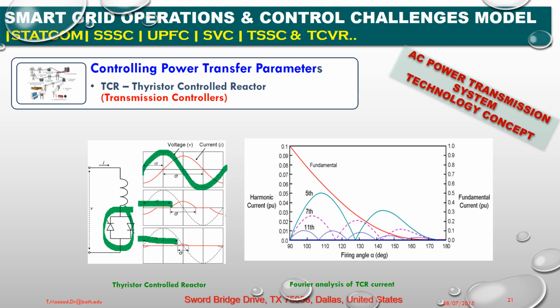Now on my right hand side, harmonic content versus firing angle, and red is my fundamental current. If we maintain 90 degrees, the 11th, 7th and 5th harmonic content will be present. As the firing angle increases from 90 to 120 degrees, the 11th and 7th reduce, and at 180 degrees they are eliminated or diminished. So 3-level quasi harmonic neutralized 48 pulse modulation is a good approach to eliminate the harmonic contents.